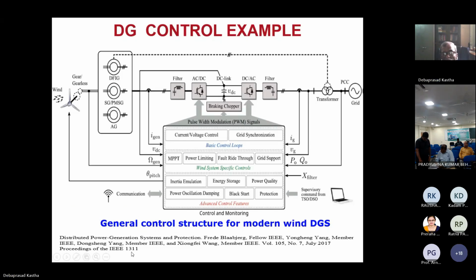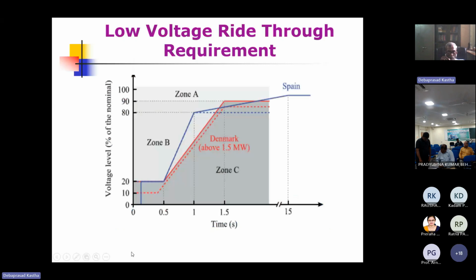This is a similar thing for a wind energy based DG. One of the major criteria in the secondary control is the grid voltage ride through. Many countries have different specifications for this low voltage ride through criteria. It basically means if there is a temporary fault on the grid, then a DG should not disconnect from the grid, provided it is in the light gray zone, that is zone B. But it can disconnect if it is in zone C. That means it is a combination of a percentage of voltage dip and the duration for which the dip persists. Depending on that, this LVRT specification has been made for different countries.